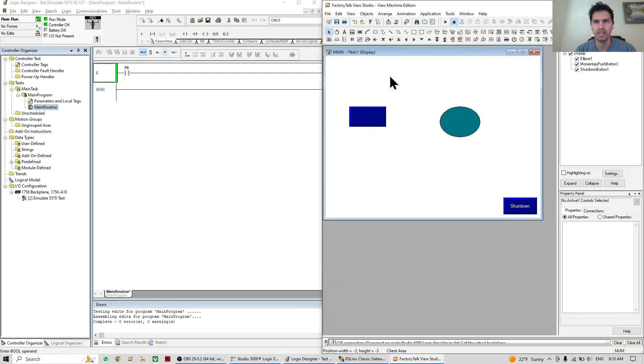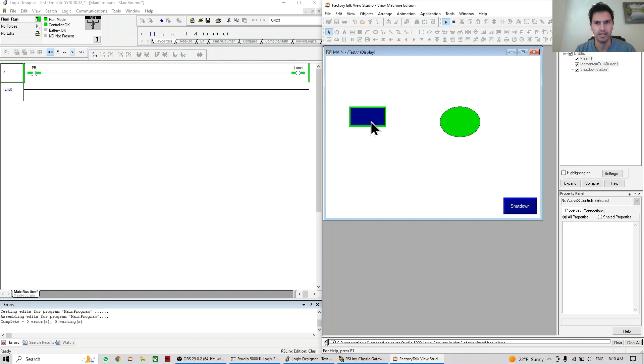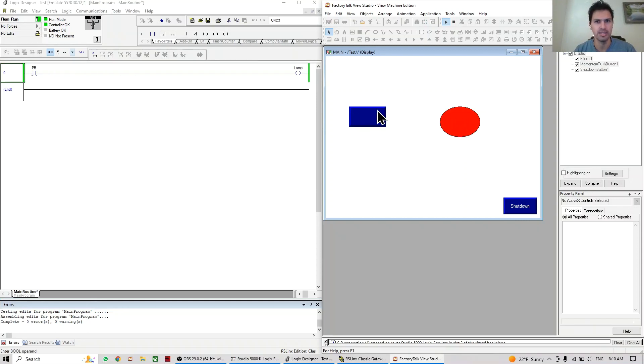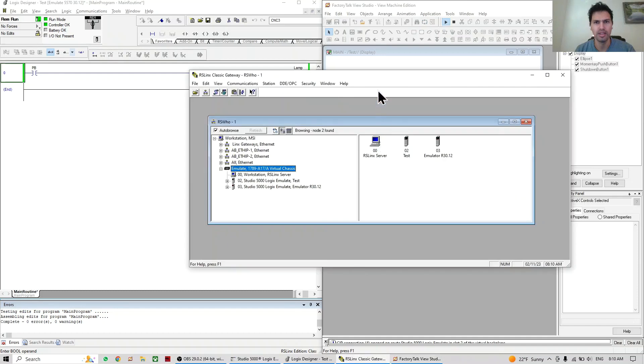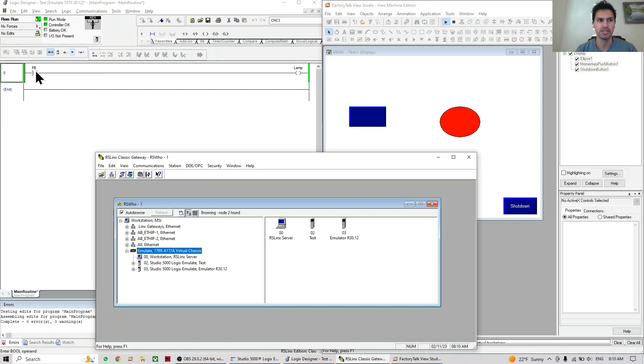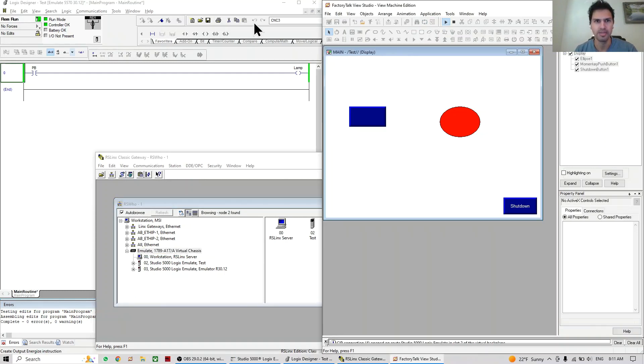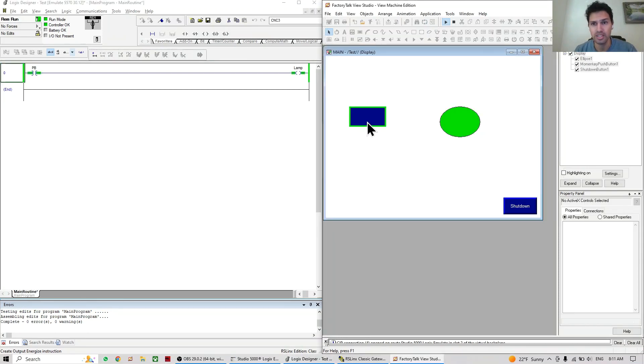And now let's see if it works. So for this, we're going to need to push here and test display. I close this, so now we can see I push the button. And what we can see is when I push the button, the lamp or the simulation for the lamp changes its color. And the same here, we can see that the push button is sending the message or the information to Studio 5000 through RSLinx. So in other words, this is coming to the RSLinx. RSLinx is sending the information to Studio 5000. Studio 5000 makes the decision that when we have this on, it means that the lamp has to be on. So that signal is coming to RSLinx and it's coming back to Factory Talk View. All that connection is made right now in just a couple minutes. So I hope you enjoyed this video and see you next time.